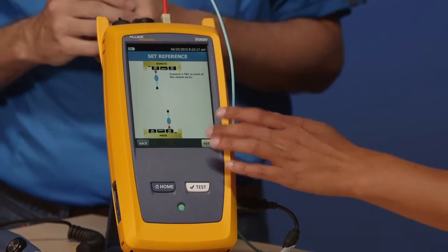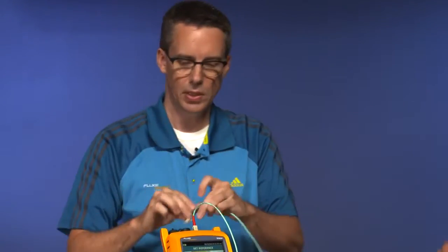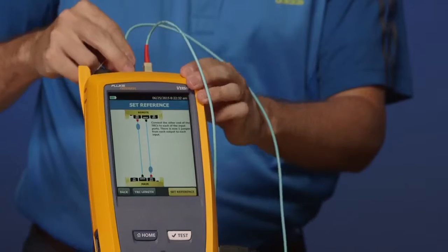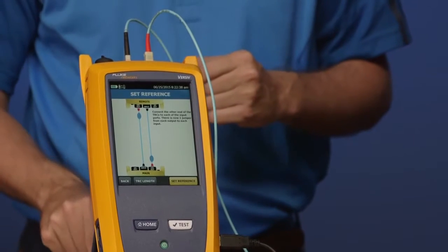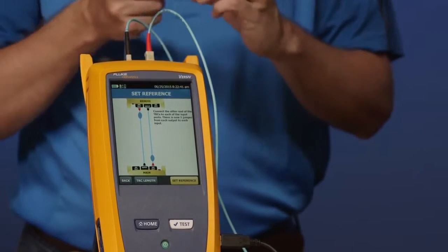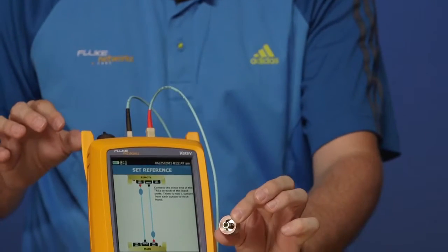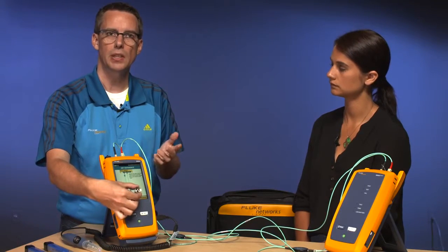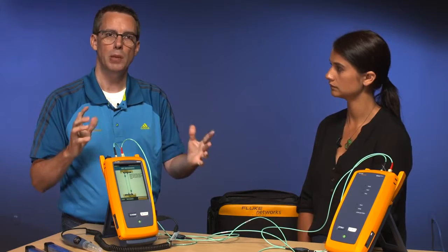Tap 'next.' The next step is to connect the two instruments together — hand the LC connection across, do a swap, and place them onto the input ports. This is LC out of the box with the CertiFiber Pro. If you need to do SC, ST, or FC testing, you can buy hybrid kits. The inputs here are LC, but you can swap in an ST adapter for ST testing, and likewise get one for SC and FC.